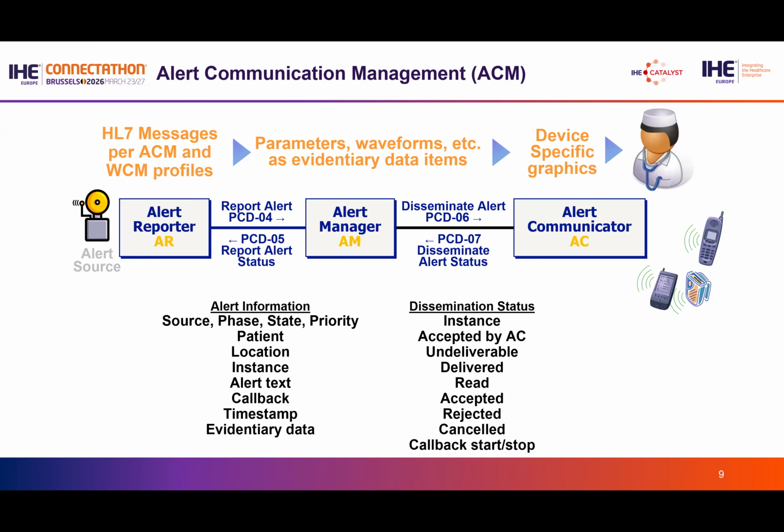So the next profile is ACM, or Alert Communication Management. If a device has an alert that needs to be addressed, either clinical or technical, this is the profile that's used. It includes any alerts that require notifications from the patient care device, including patient-level alarms that need to be delivered immediately to clinicians, or workflow step notifications or advisory events about the device condition.